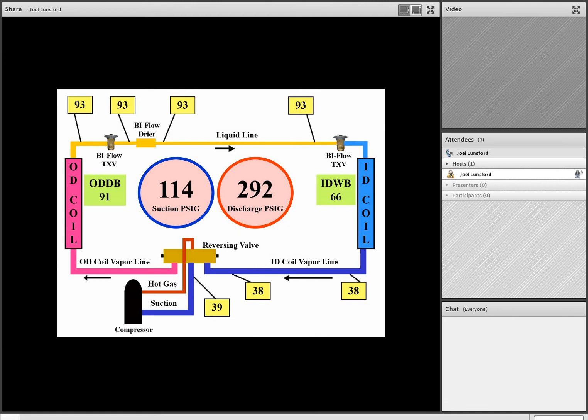So I'll give you a little bit of time to do this as we move forward with some of these interactive service calls. We want to look at our pressures and temperatures. I'd like you to work out your superheat and your subcooling. Look at all the temperatures throughout the refrigeration circuit as we pick the pace up a little bit. In our example here, we see our suction pressure is a little bit low.